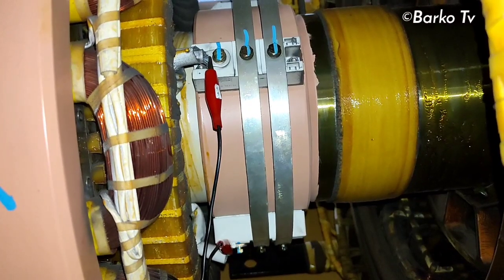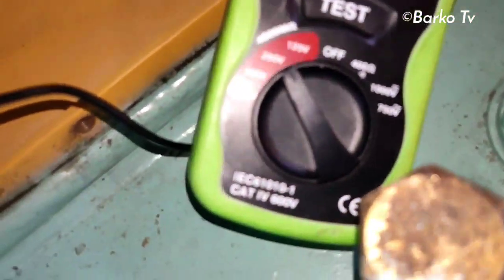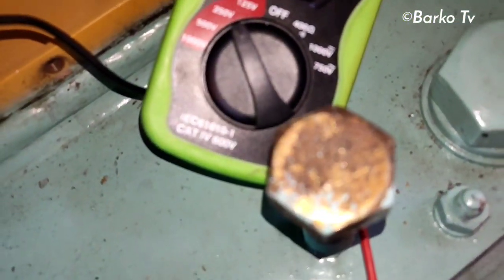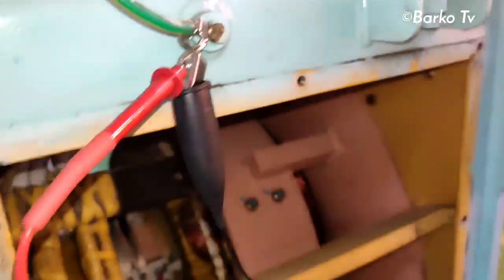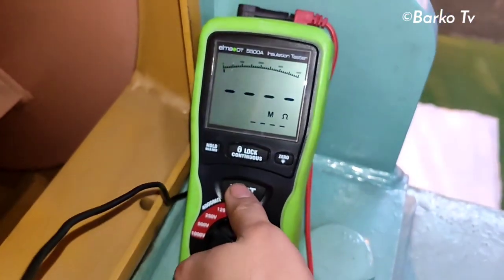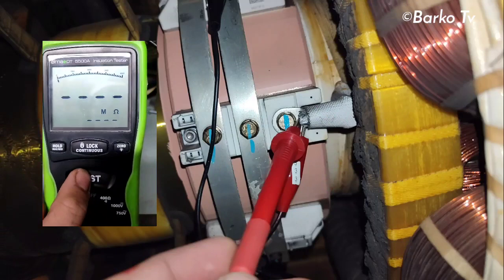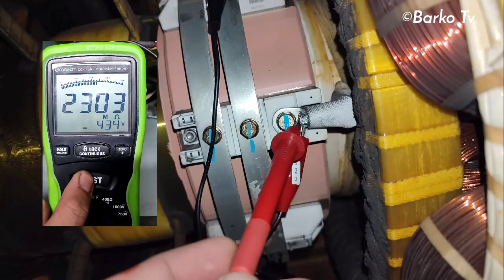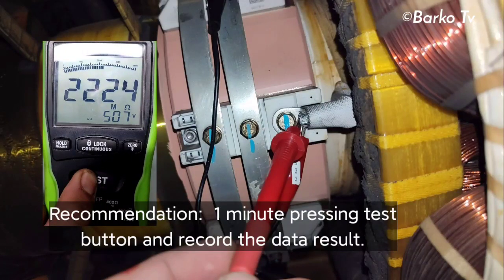After all five terminals are connected — one, two, three, four, five — we use the insulation tester. Set it to 500 volts as per the manual. Connect to ground, select 500V, then press the test button. The reading is almost 0.005 — select one of those terminals and press the test button. Our IR tester reads 2247 or 2250 mega ohms. The range of our IR tester is 4000 mega ohms.